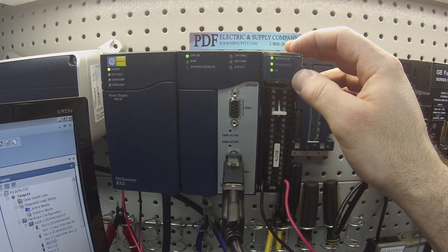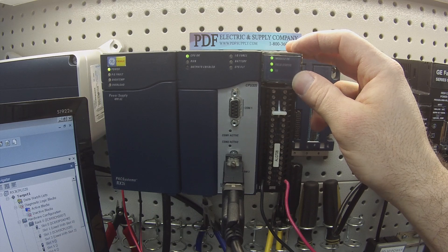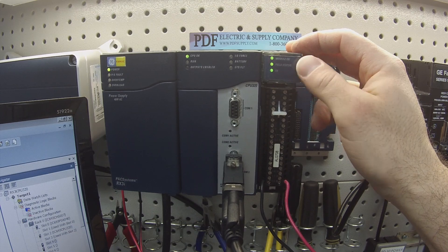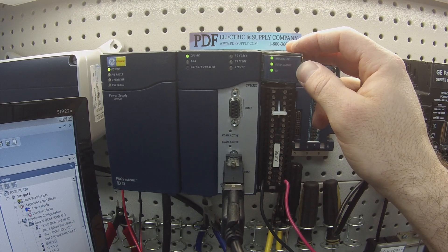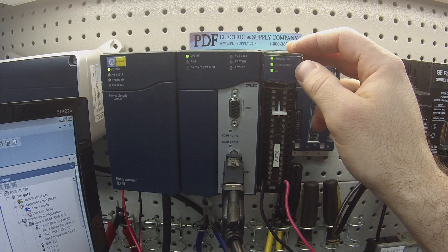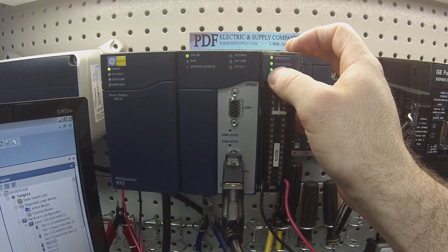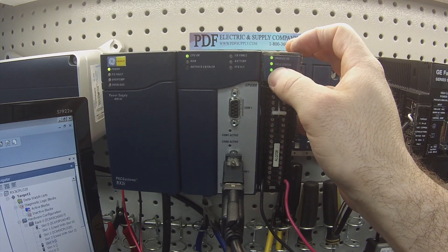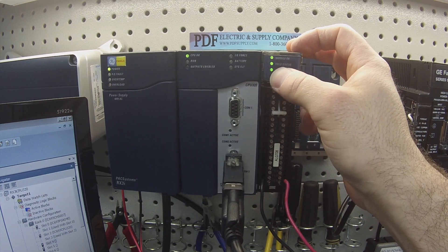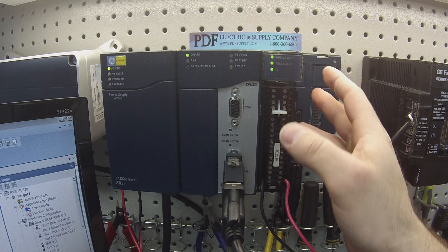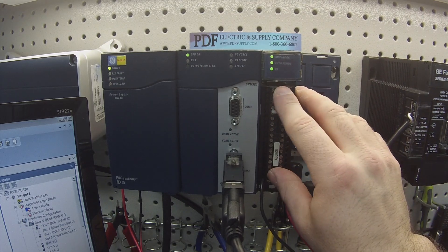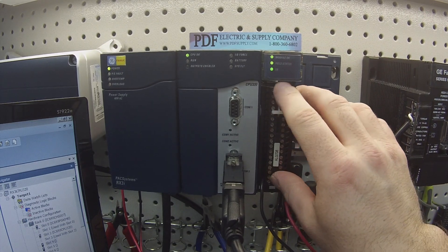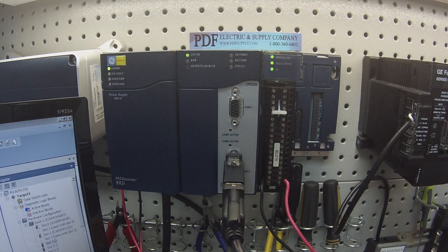If for some reason you have a module that you don't have a module OK light blinking green or no light at all and your field status when you power up your 24 volt power supply is not working, there's likely something immediately wrong with this module and may need replacement or repair.